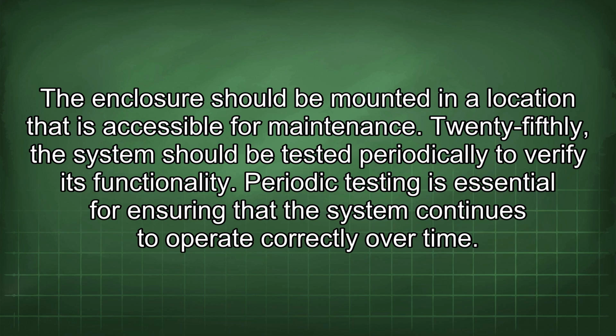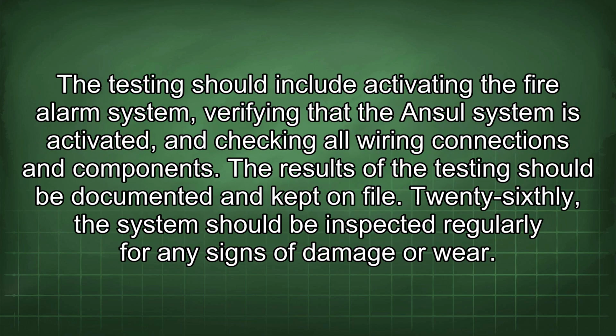Fifthly, the system should be tested periodically to verify its functionality. Periodic testing is essential for ensuring that the system continues to operate correctly over time. The testing should include activating the fire alarm system, verifying that the Ansul system is activated, and checking all wiring connections and components. The results of the testing should be documented and kept on file.